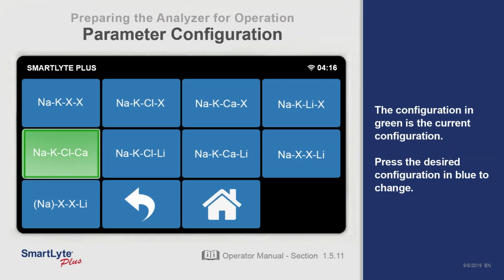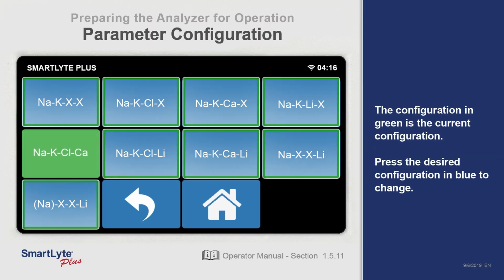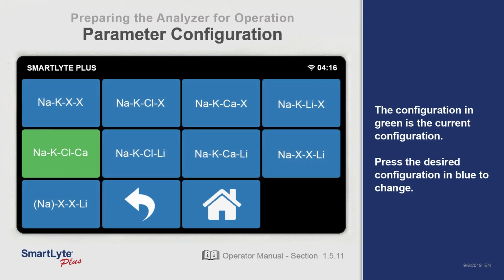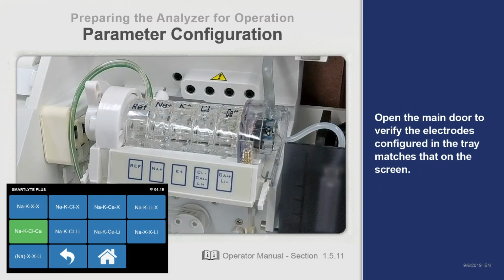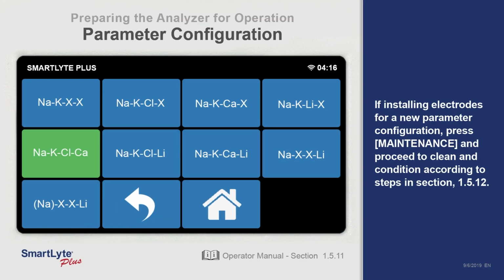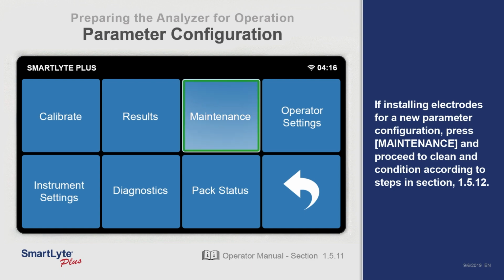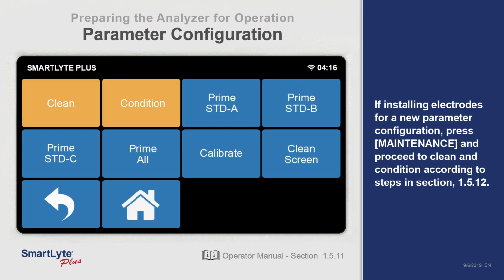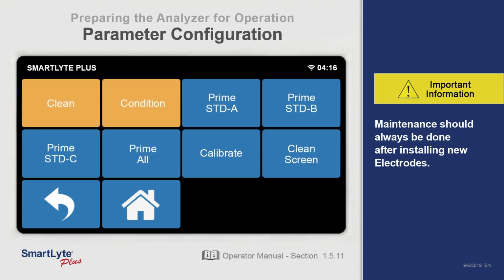The configuration in green is the current configuration. Press the desired configuration in blue to change. Open the main door to verify the electrodes configured in the tray match that on the screen. If installing electrodes for a new parameter configuration, press Maintenance and proceed to clean and condition according to steps in section 1.5.12. This should always be done on electrodes after installation.